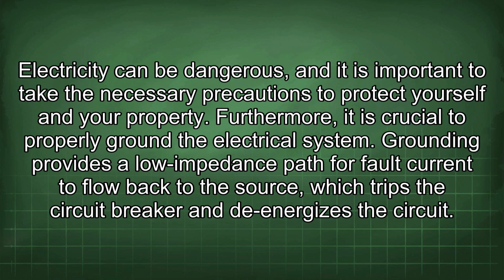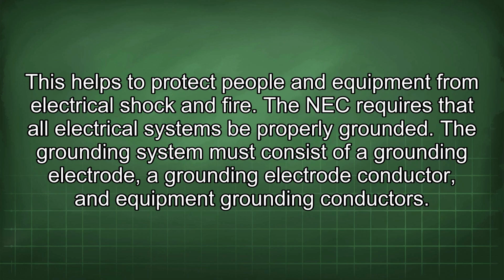Furthermore, it is crucial to properly ground the electrical system. Grounding provides a low impedance path for fault current to flow back to the source, which trips the circuit breaker and de-energizes the circuit. This helps to protect people and equipment from electrical shock and fire. The NEC requires that all electrical systems be properly grounded. The grounding system must consist of a grounding electrode, a grounding electrode conductor, and equipment grounding conductors.